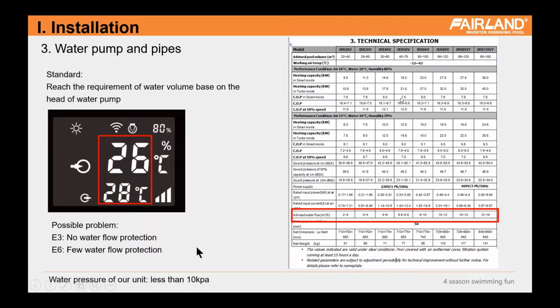This often happens because they forgot to open the valve to make the water flow into the heat pump. So after the heat pump is running, it will cause E3, the no water flow protection.